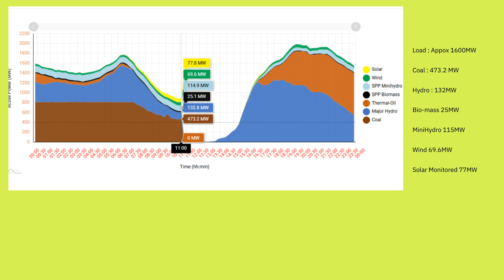It was a sunny Sunday with maximum solar generation and the lowest electricity demand in the country. Since small-scale solar output isn't monitored, the expected load at the time was around 1,600 megawatts, while unmonitored solar generation was estimated to contribute 600 megawatts or more. Baseload generation came from coal-fired units, which despite a total capacity of 900 megawatts, were operating at a reduced level of 473 megawatts. With most solar capacity unable to respond to sudden fluctuations and coal units being slow to adjust, the system was in a precarious position, relying on limited fast reserves for stability.